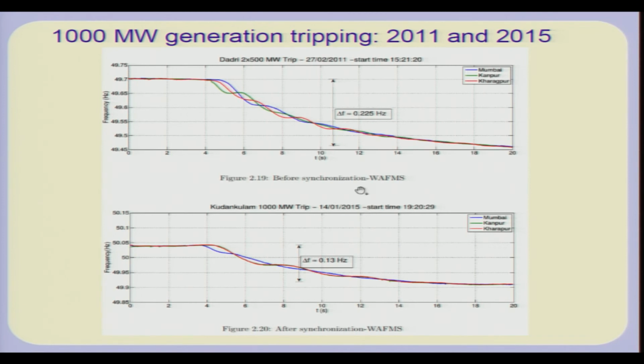In fact, because we were monitoring these measurements over quite a bit of time, what we find is that from 2011 to 2015 there has been a change in the characteristic of the grid. If you look at it, the frequency drop for a 1000 megawatt trip which took place in 2011 is about 0.225 hertz, slightly more than that, whereas in 2015 it is only 0.13 hertz. You also find the slope of this characteristic, that is the initial rate of drop of frequency when there is a sudden load generation imbalance, which is dependent only on the overall rotating inertia of the system.